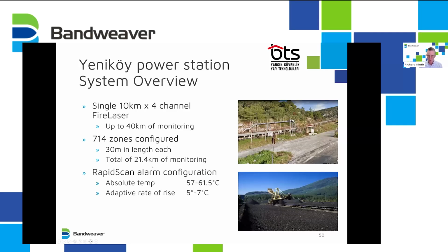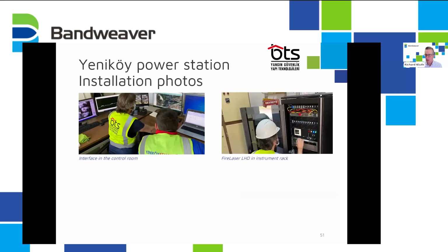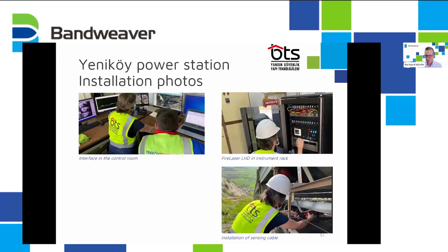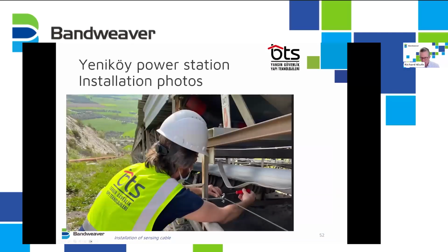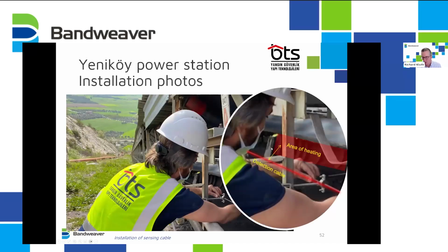So they had 20 kilometers of monitoring. The RapidScan, the absolute temperature they set between 57 to 61 degrees, and the adaptive rise quite low in what I've seen, 5 to 7 degrees C, and it was integrated with the Panasonic CCTV. We've got some photos here, photo in the control room, the unit in the rack, the fiber installed, a training session. When we look at the fiber install here, you can see this is the conveyor belt. These are the rollers, and this is the source where the bearings may heat up. So they've got the cable as close as possible to the area of the heating.